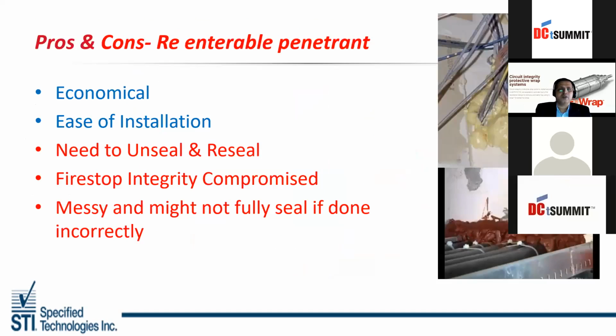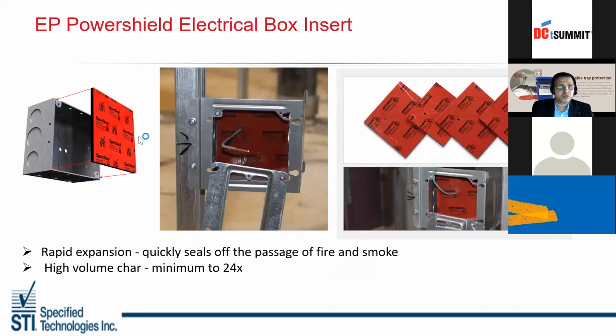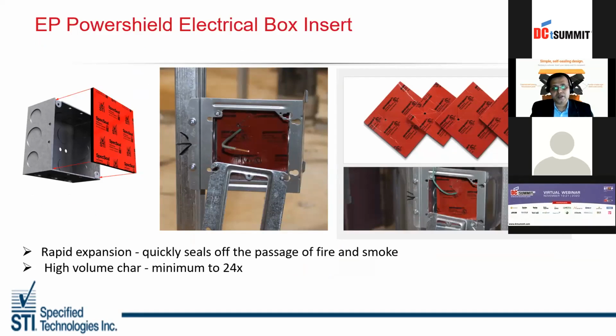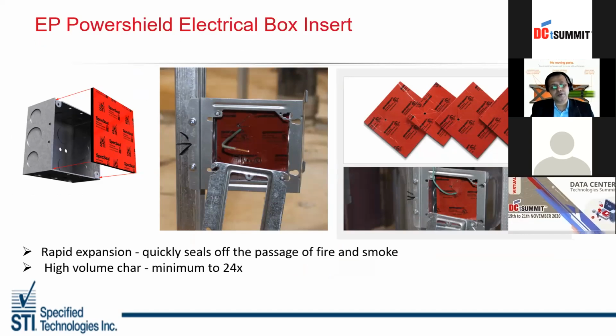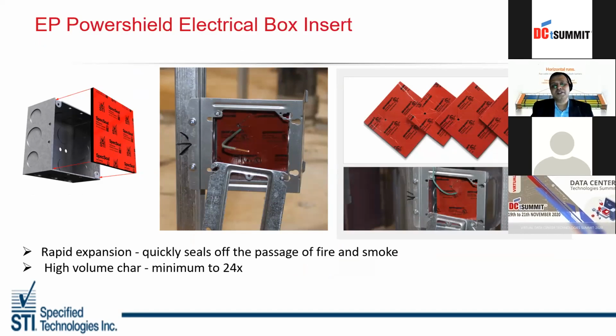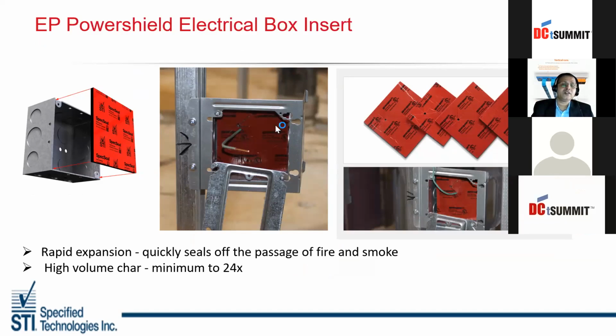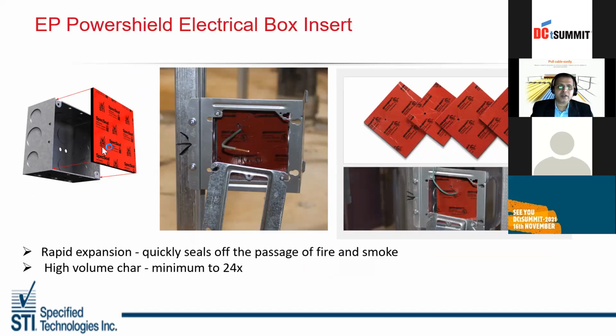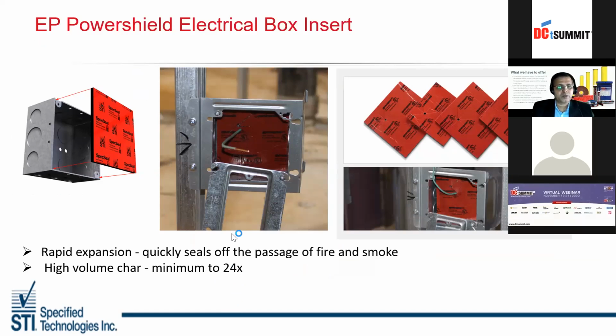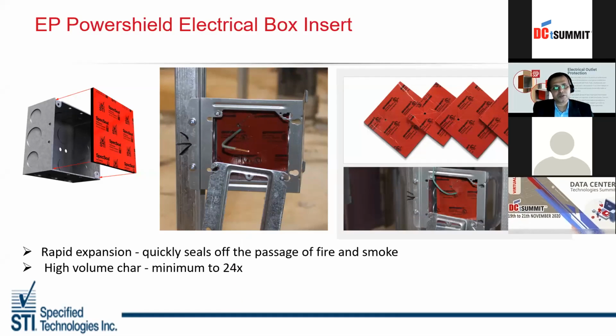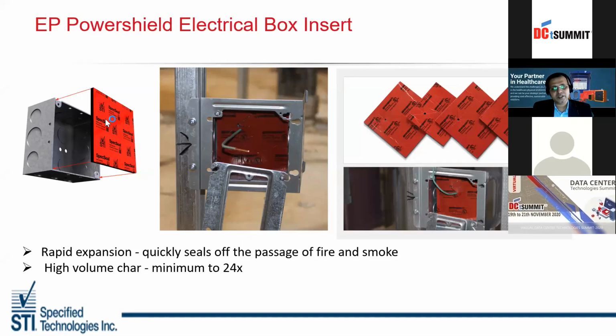Here we have one more product which is called EP Power Shield, or we call it box inserts also. These products are used in scenarios where you have a gypsum board or a concrete wall, wherein there are chances of a short circuit in those concealed boxes. So this product will expand almost 24 times its size or volume to stop the fire and smoke traveling from one conduit box to the other conduit box. So here also it's an easy to install product.